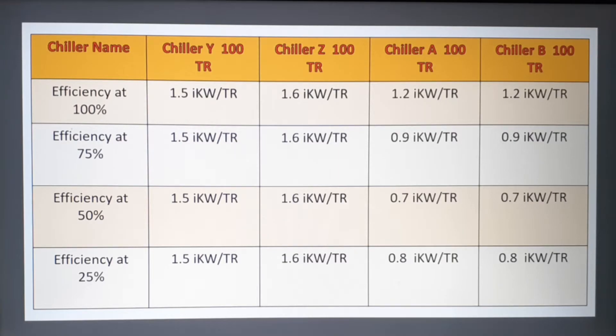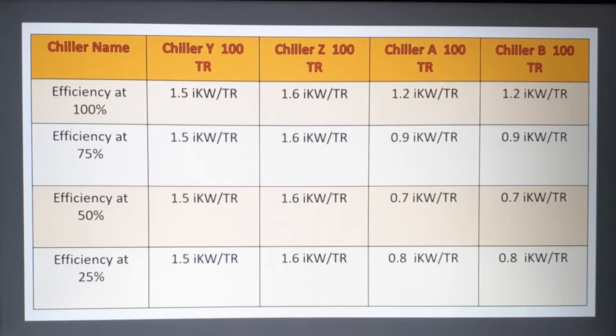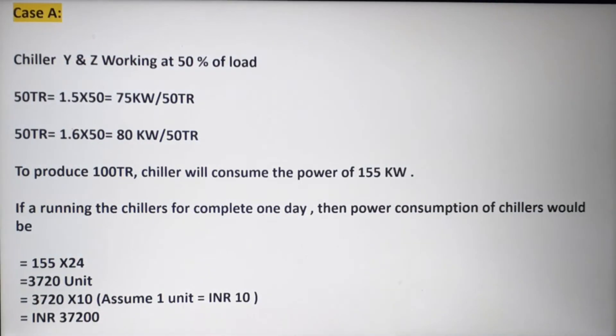If you have a combination of VFD and non-VFD chillers, preferring to run VFD chillers will definitely give you energy savings. I am considering four chillers with a total capacity of 400 TR, and my current load is 100 TR. In Case A I will manage the load using chillers Y and Z, and in Case B I will manage it using chillers A and B — this example will show how much energy and cost can be saved.